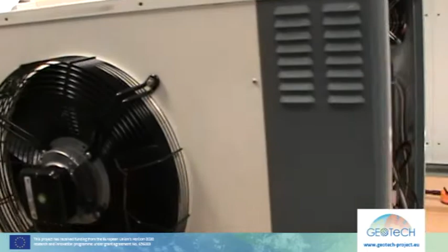Last but not least, this is a multifunction unit with full recovery of condensing heating capacity. Instead of rejecting heat into the air or underground during summertime, we can use it especially for sanitary hot water purposes, allowing cooling and heating at the same time. With this kind of functionality, the system can achieve a really huge COP.